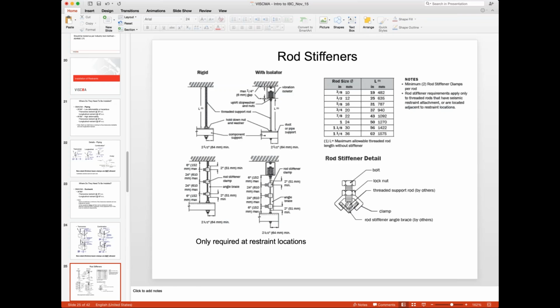And then when you have it with an isolator, that sketch shows that you are now technically using that hanger box as part of your compression system to get that compression load back up to the building. And as such, you're going to need to install, and it's typically on all of the manufacturer's submittal drawings, a stop washer with a nut underneath the box, so when you push on the rod, it just doesn't go through the box. And this way you can carry your compression load, and those boxes are typically designed for that, since they're also designed, at least on the tension side, for large safety factor over their standard spring capacity.